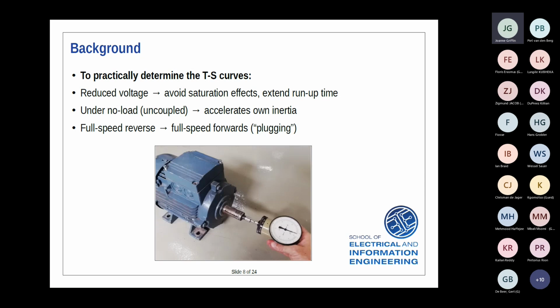Okay, so how do we do these torque speed tests? We do it at a reduced voltage, first of all, to avoid saturation effects. We don't want the current to go over the rated current, otherwise the machine saturates and then you get very inaccurate results. When I say reduced voltage, it's typically 0.3 per unit, 0.4 per unit, so very low. This has an advantage for us because it extends the run-up time. Instead of a direct online start taking seconds or milliseconds, at a very low voltage we have a very extended run-up time, maybe over a minute. So we can take lots of data samples in a minute as the machine accelerates. That's quite helpful for us.